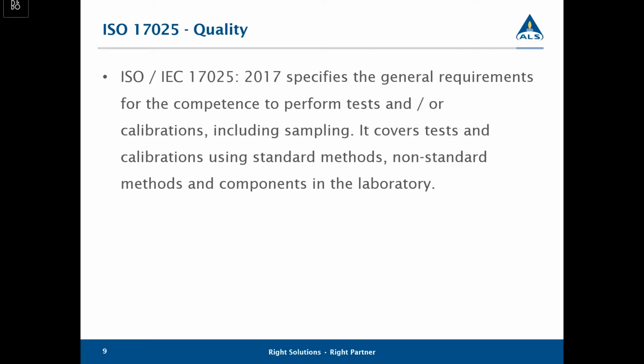So this is a quality standard, and labs that are accredited to this get audited externally to ensure that the tests that they're performing are up to standards, that we're calibrating properly, that we're keeping all of the quality documents that we should, that we're running statistical process control samples, that we're recording those, that we have everything documented, and that we're doing everything as the method states. We get externally audited each year to hold this accreditation.